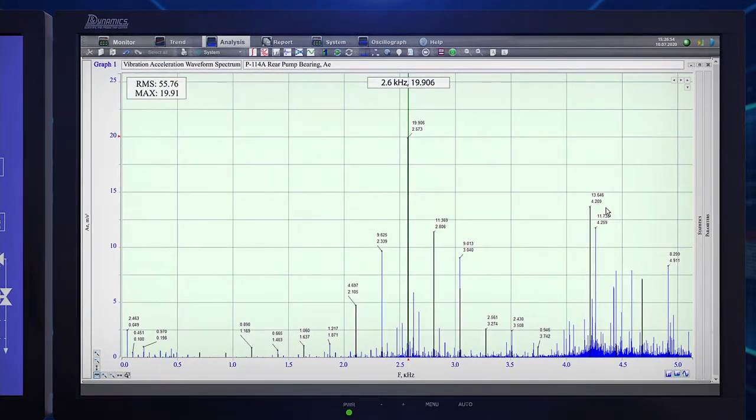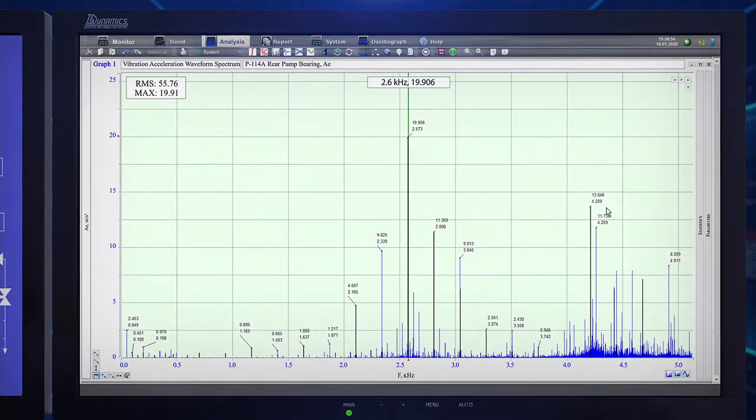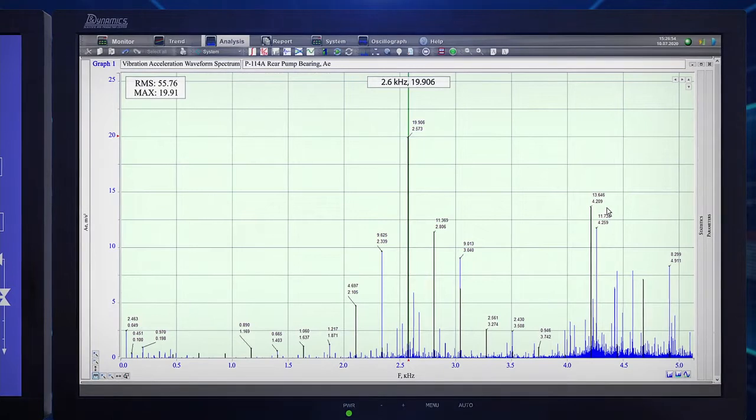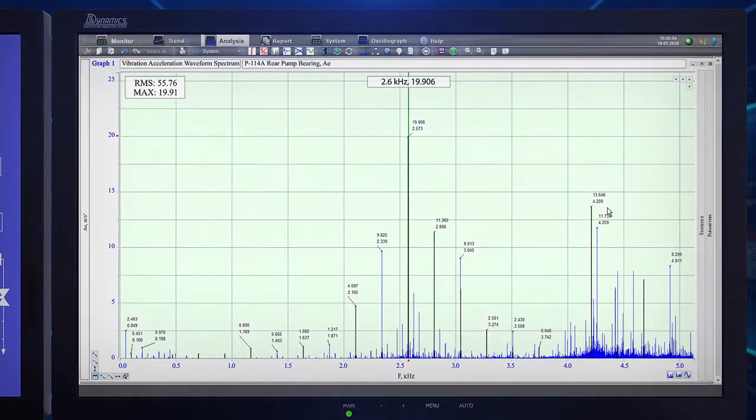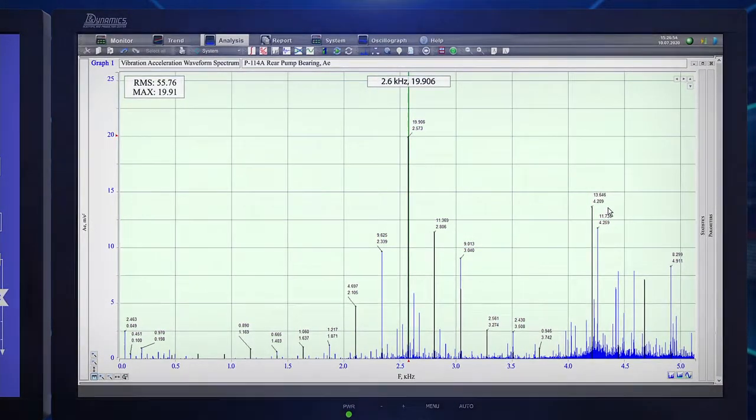Also, there is a sign of a bearing defect in the vibration signal spectrum and broadband vibrations along with multiple noise components which can only mean the assembly or mounting defects.